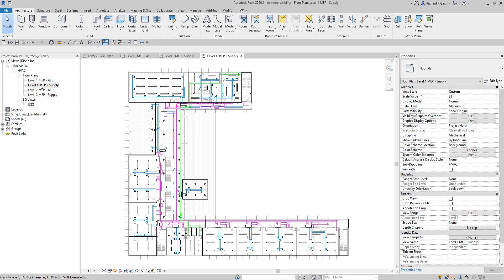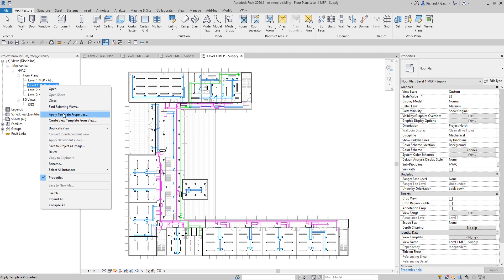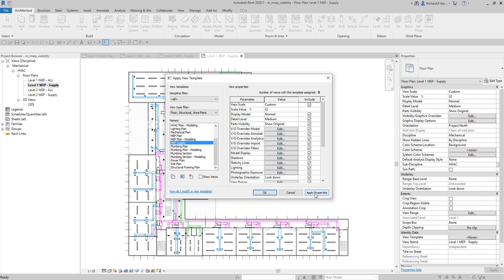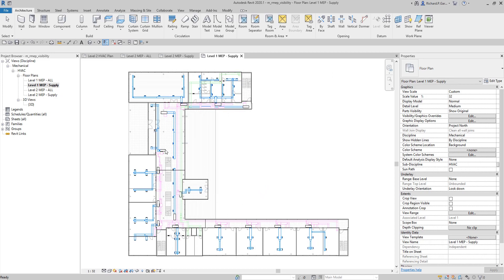All you have to do is right-click the view and select 'Apply Template Properties', then look for MEP Supply. This applies the view properties from the MEP Supply view template. Select OK and there you go - it's now highlighting the supply system. You can apply this to any view very quickly.